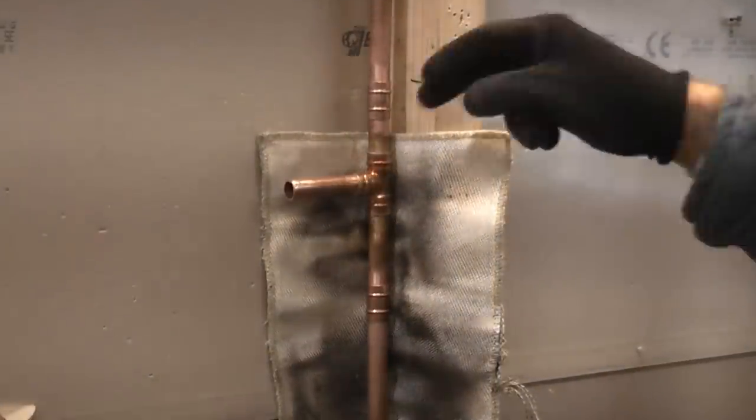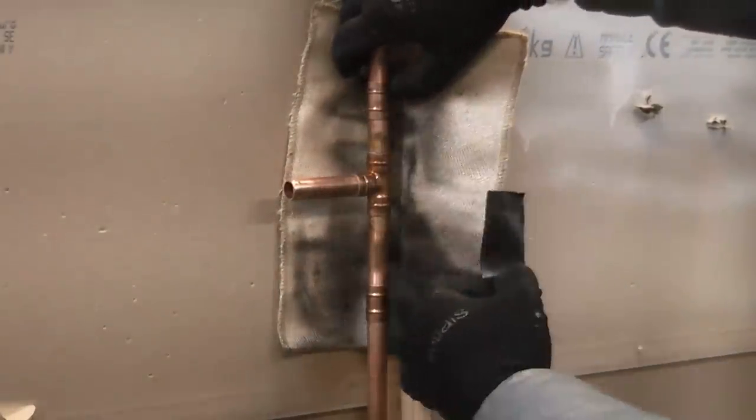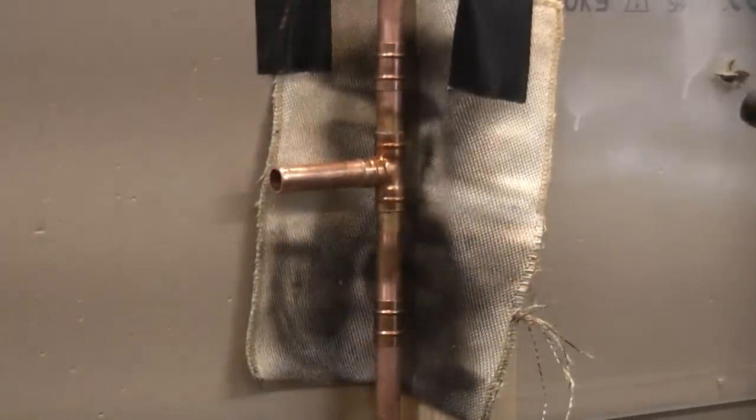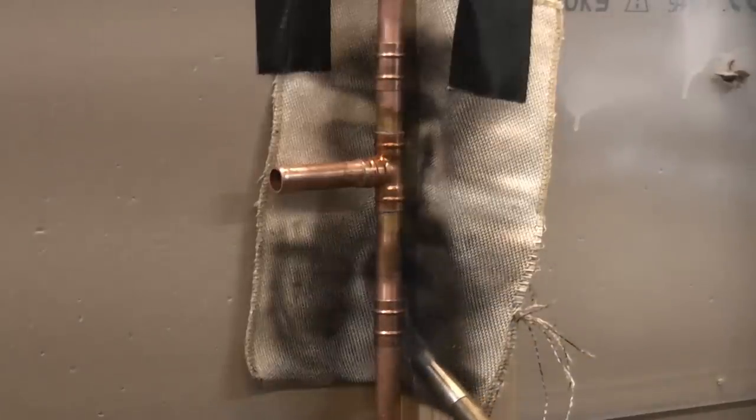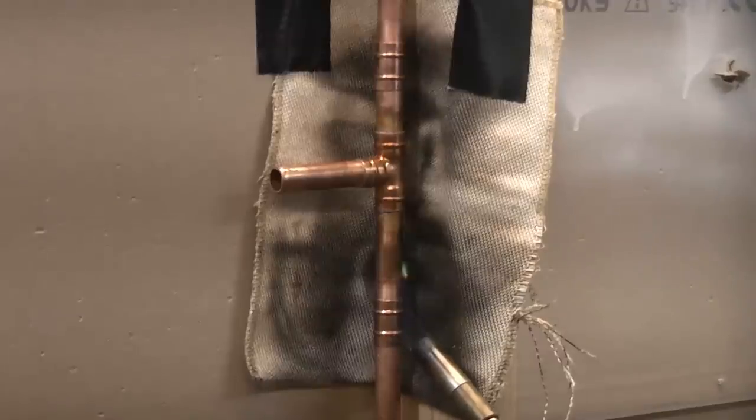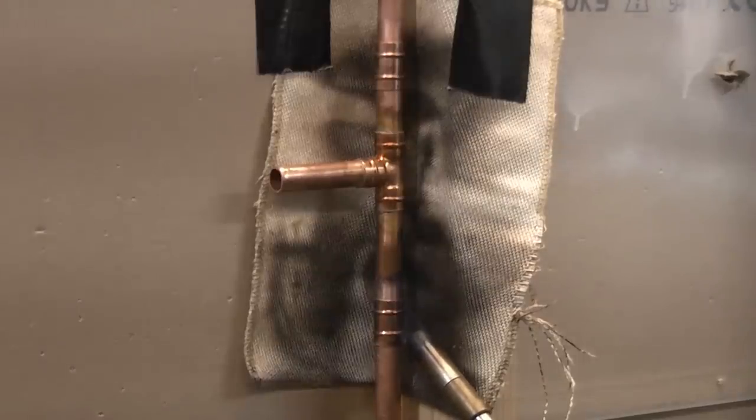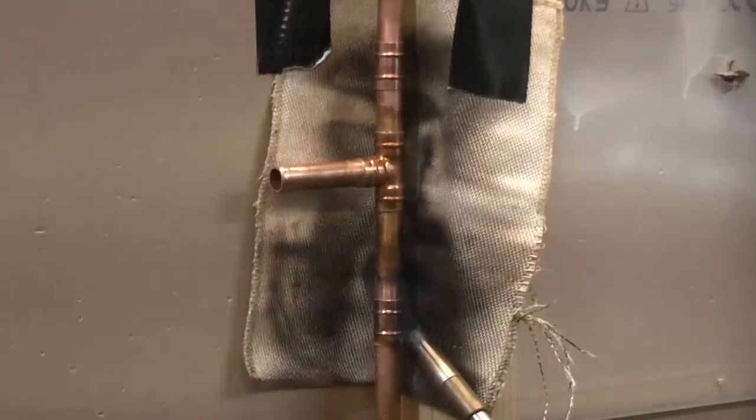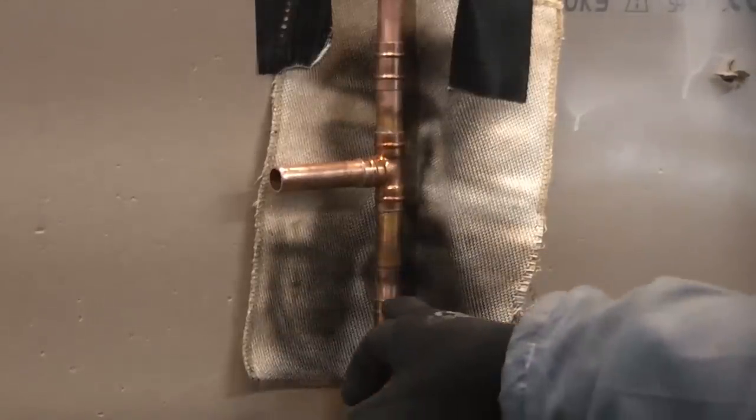Because we're soldering near the timber and plasterboard I'm just going to use the heat mat. I'm just going to tape that in position to prevent anything from getting scorched or set on fire. Again, all we need to do is take the blow torch and apply a little bit of heat to each of the fittings. You can remove the heat once you see the solder exiting from the fitting.